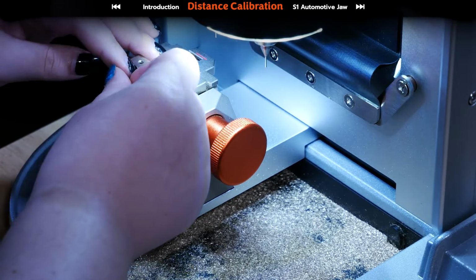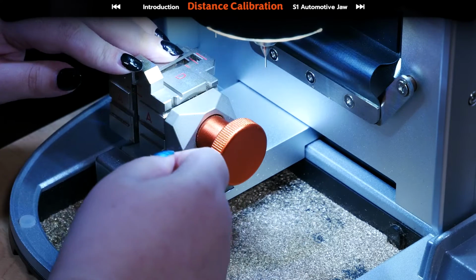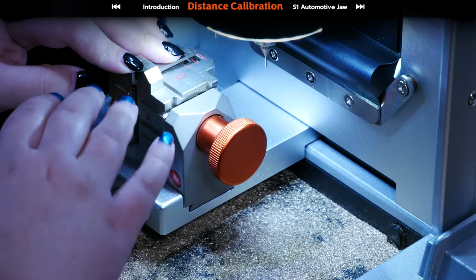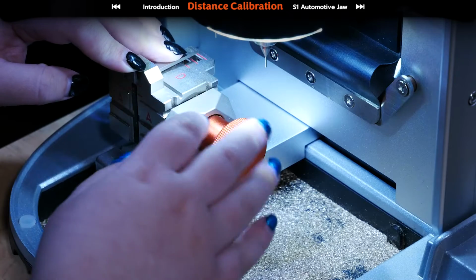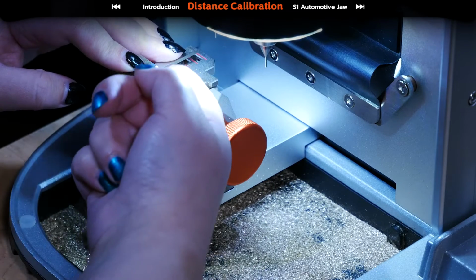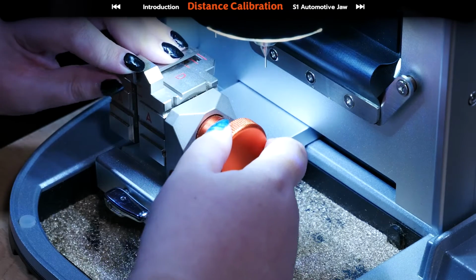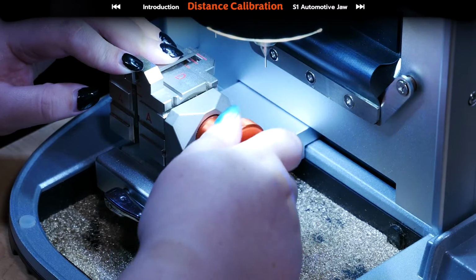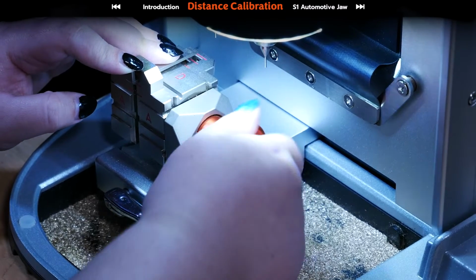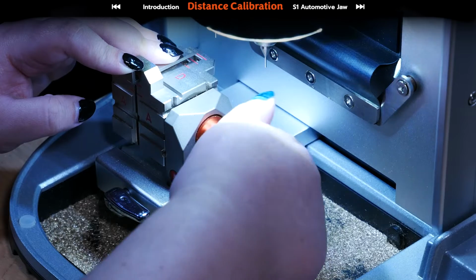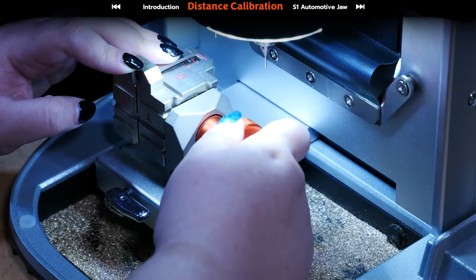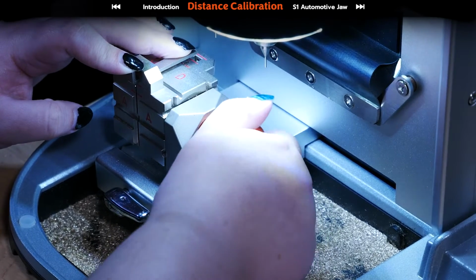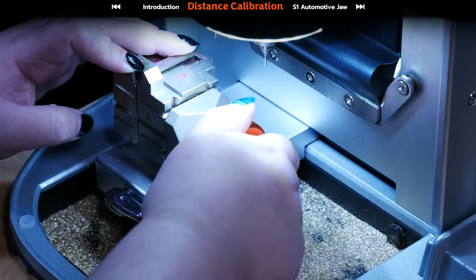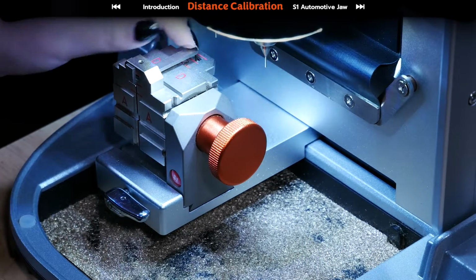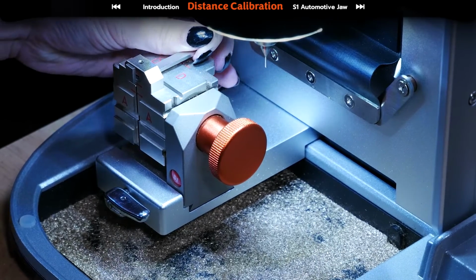We're going to insert it the long way, and I usually use my fingers here to kind of make sure that it's staying straight and leveled while it's resting on this little bridge. And you're going to line up the tip to the second red line. And then tighten up the screw on the side, this little orange knob, until you meet resistance. And then you can't move this at all.